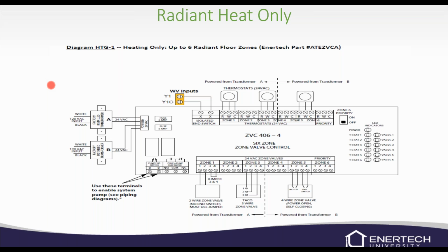I would like to mention on this that on these zone valves, if you have a 2-wire zone valve, you will have to jumper the 3 and 4 terminals. That 3 and 4, that's basically your end switch. It's letting it know that it's open or closed. Well, this 2-wire valve doesn't have an end switch, so we must use the jumper. These 2 X terminals are used for enabling the system pump.